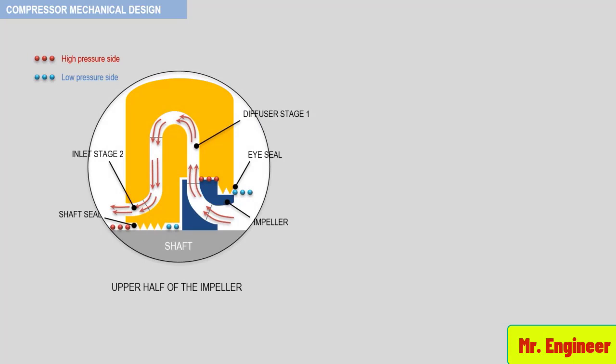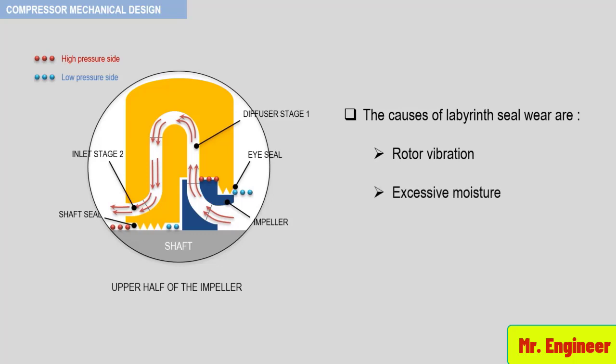The causes of labyrinth seal wear are rotor vibration, excessive moisture, and fouling. What you need to understand is that if your centrifugal compressor head and efficiency fall off greater than 10%, then your compressor should be inspected at the next opportunity, if the compressor is known not to be fouled.